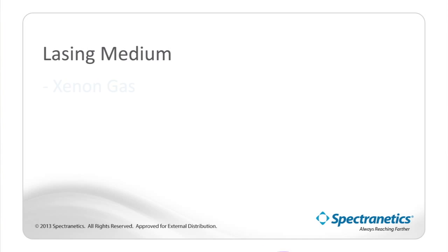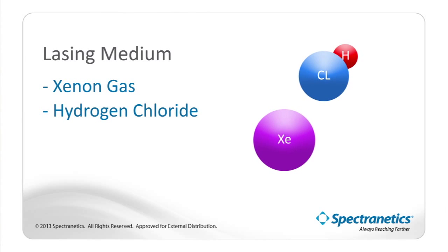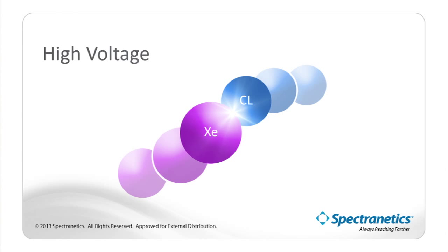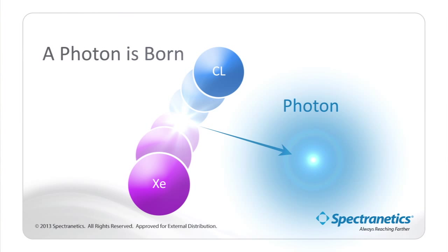The lasing medium used when performing laser atherectomy is a mixture of xenon gas and hydrogen chloride. This mixture is then bombarded by extraordinary voltages, and we get a xenon chloride molecule. As we continue to bombard with extraordinary voltages, the electrons jump in orbit, circulating in an unstable orbit. When they do this, they release a packet of light — a photon — and that is how all laser light is generated.